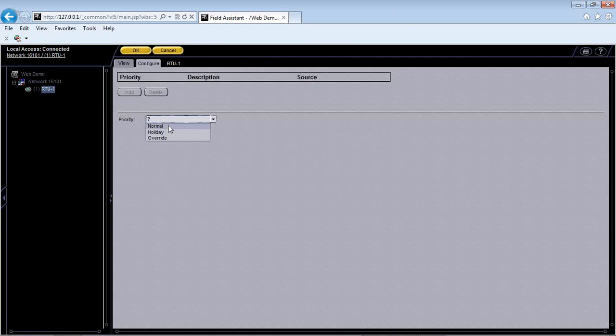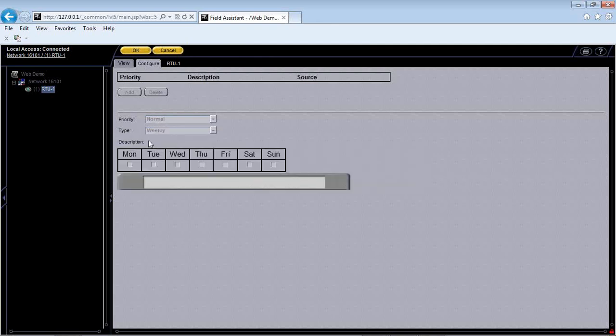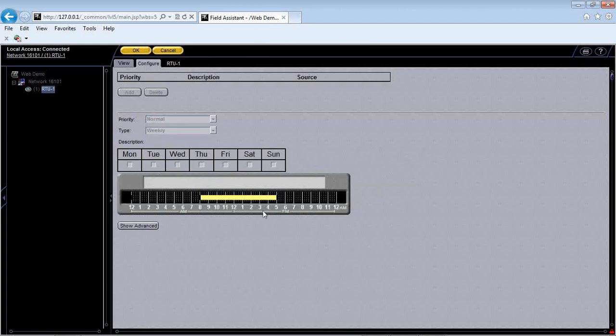You can do a holiday schedule, which tells the unit go unoccupied from this time to this time. And you can do an override schedule, which will actually override both the holiday or the normal schedule based on what you put in there to go occupied. So if I do normal, I want to choose a weekly schedule so I can select the times of the week that I want it to go on. Let's say this is going to run Monday through Friday, so I check these boxes. This is my time that I'm actually scheduled right now.